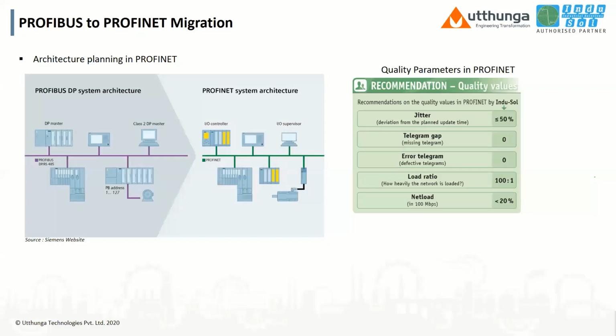That's one solution. But even so, if you are changing to PROFINET, what do you need to look at? You need to check complete quality parameters. Like in Profibus, we have some quality parameters and standards. Right now, we've gone through the 1 meter rule or shielding, error telegram, repeat telegram, these types of things. But in PROFINET, quality parameters are jitter, load ratio, and net load. These 3 points have to be taken care of, otherwise your network will be very vulnerable.